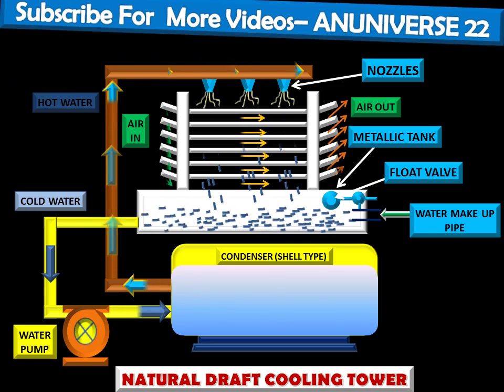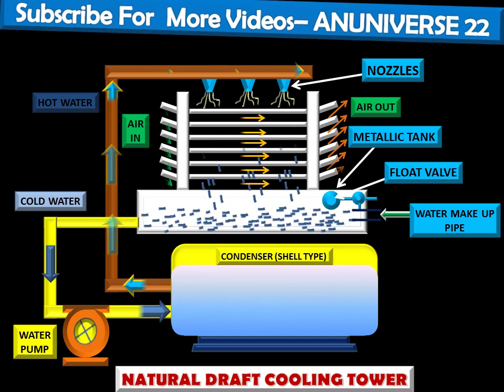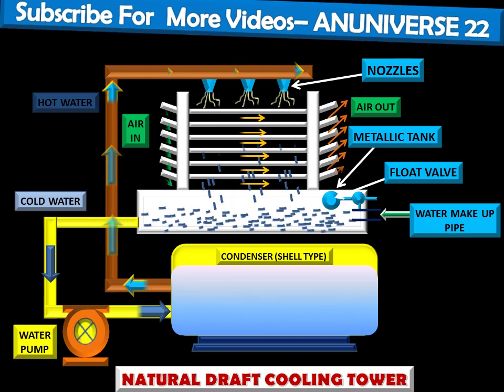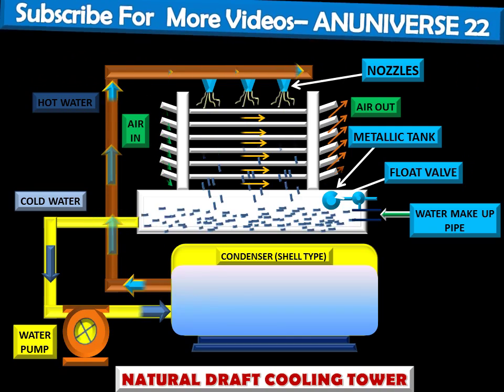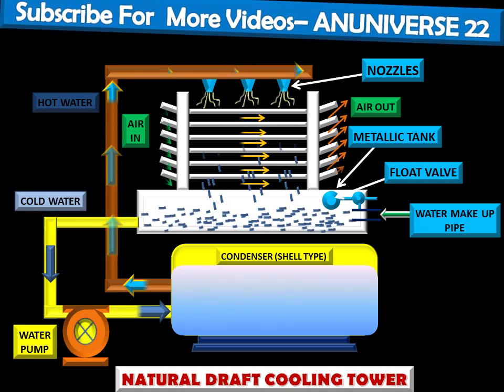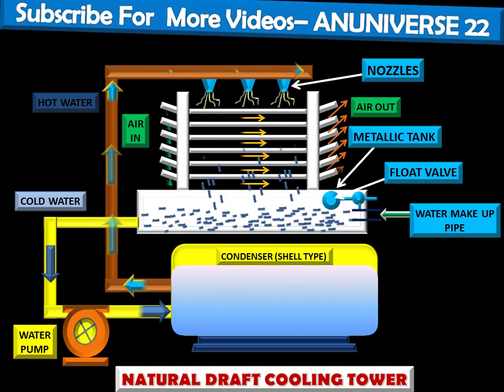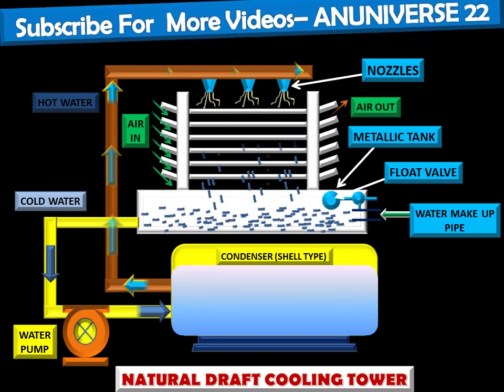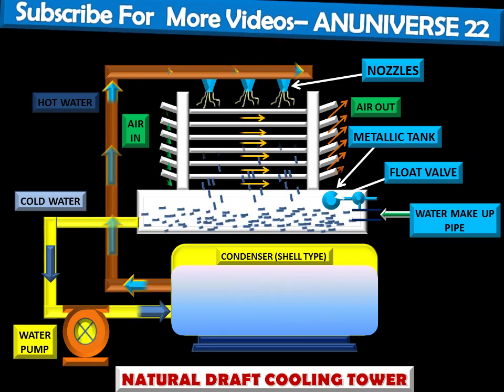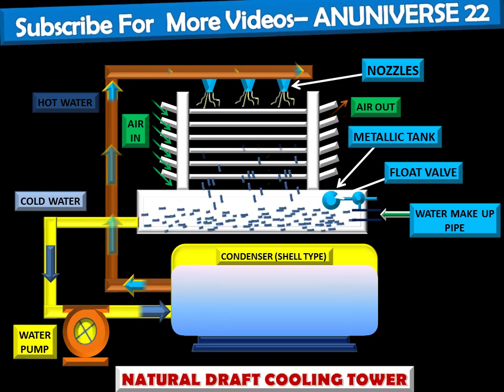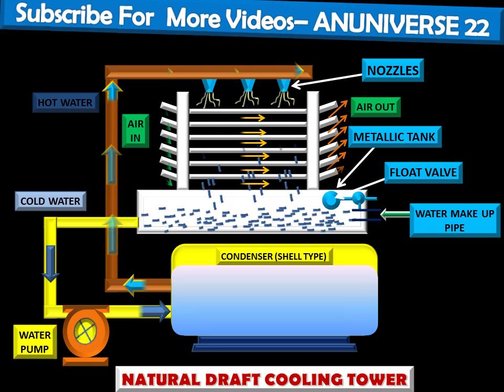The natural draft cooling tower is located as per the available space. If enough space is available, it is installed in open air outside the building. But when space is limited and natural air is restricted, the roof of the building is the best location. There are some limitations: the efficiency of natural draft is low, and it occupies more space. However, the manufacturing cost is less, and the process used to cool hot water relies on natural air.